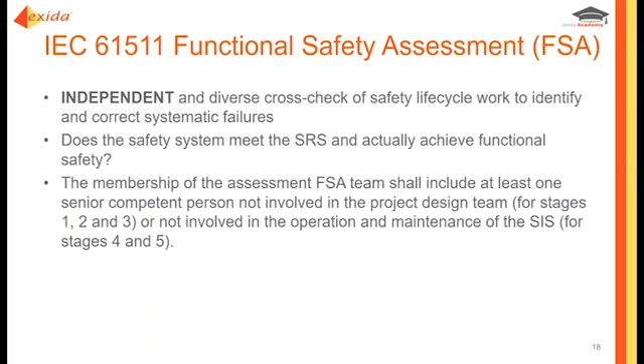They think, okay, we just need to do FSA 3. The way that the standard is worded would tend to suggest that until you read 5.2.6.1.4, where it says, an FSA team shall review the work carried out on all phases of the safety life cycle prior to the stage covered by the assessment that have not been already covered by previous FSAs. So what does that mean?